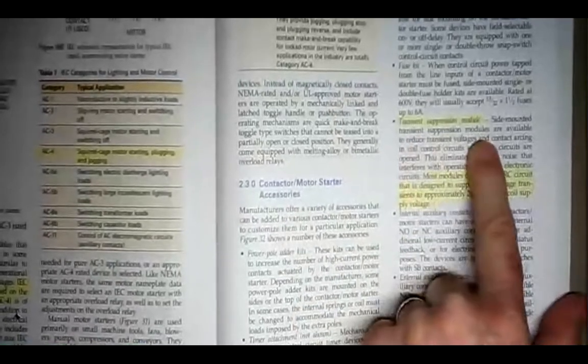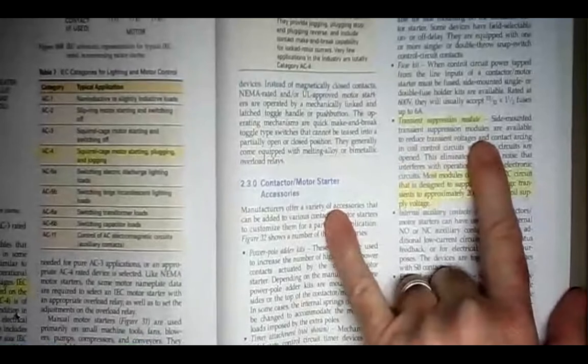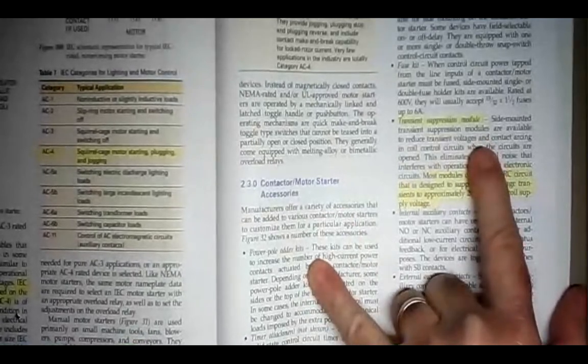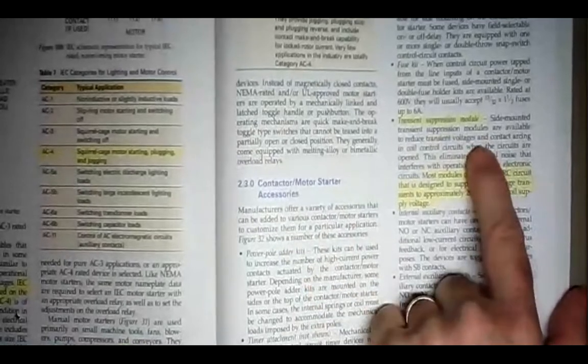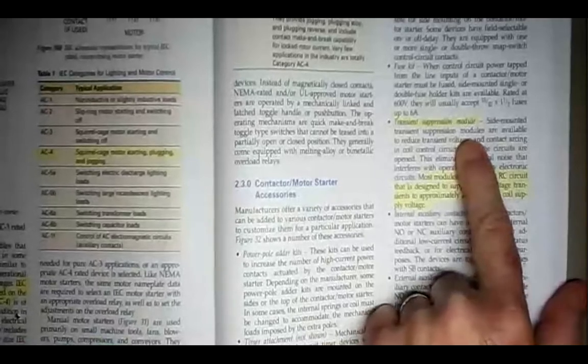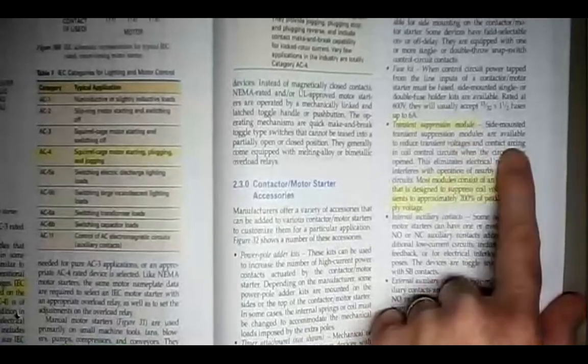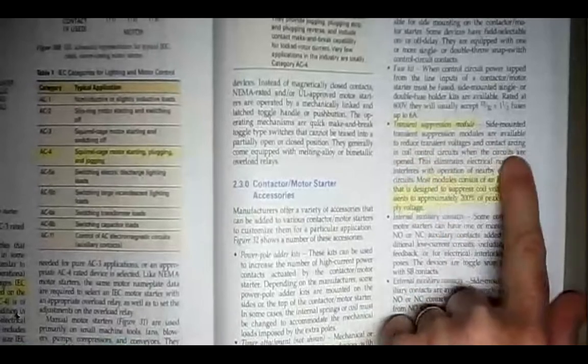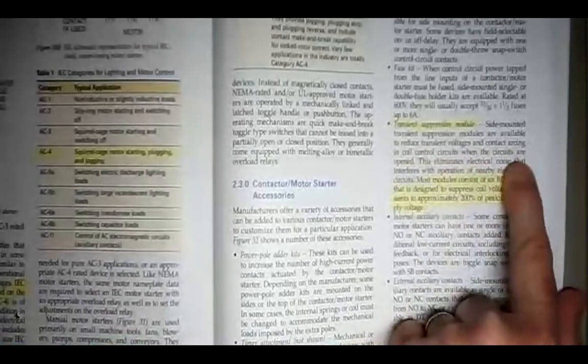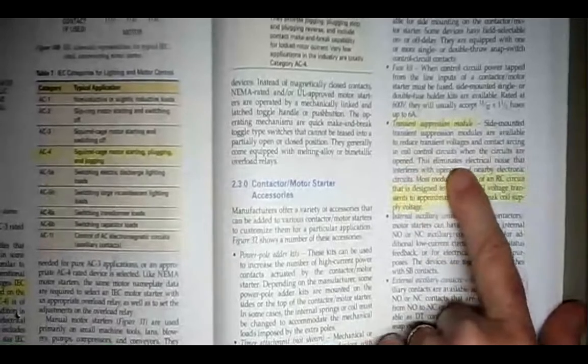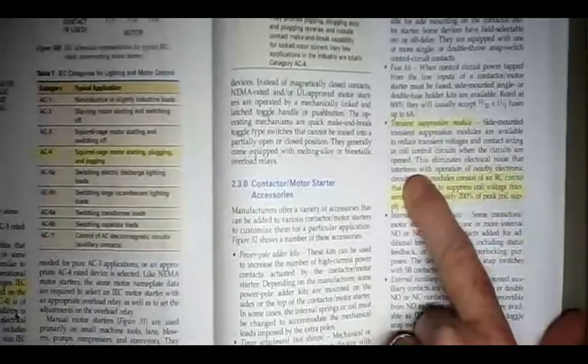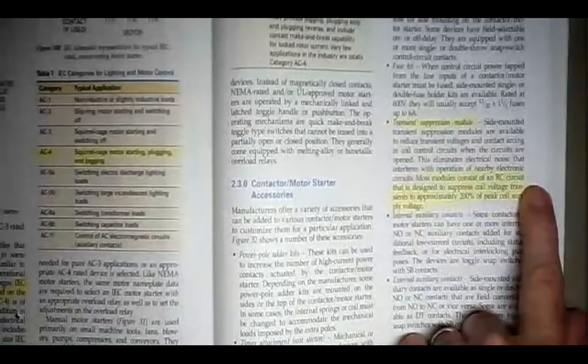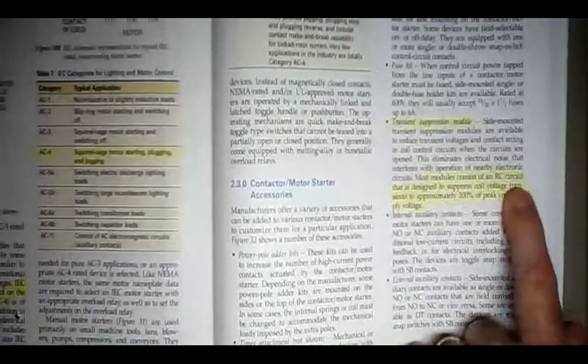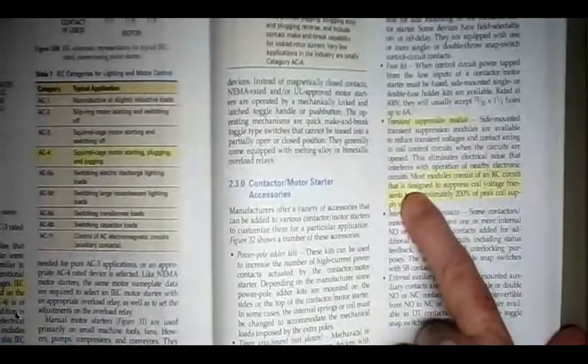Here on page 29, on the right-hand side, I have one bullet highlighted here. Transient suppression module. These are contactor motor starter accessories, things that you can get. You can get a power pole adder kit, timer attachment, fuse kit, and here's the transient suppression module. So it suppresses transient voltages. Side-mounted transient suppression modules are available to reduce transient voltages and contact arcing in coil control circuits when the circuits are opened. This eliminates electrical noise that interferes with operation of nearby electronic circuits.